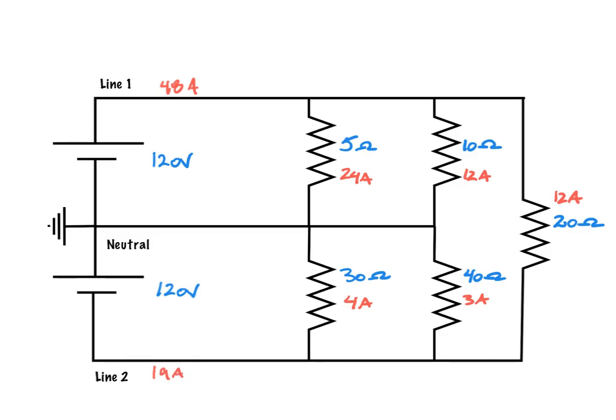So now we have a situation where we're unbalanced, because our line 1 does not equal our line 2. And that is where the whole idea of the neutral comes in. The neutral carries the unbalanced current. So what we're going to do here is we're just going to take the line 1, 48 amps, we're going to subtract 19 amps from there, and we're going to get a neutral current of 29 amps.